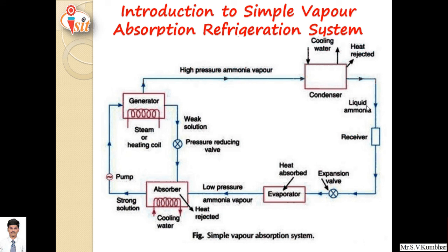This is the simple vapor absorption refrigeration system. Compressor is replaced by this generator and absorber unit. In the generator, we generally use a refrigerant plus absorbent solution. Most of the time we prefer aqua ammonia solution — ammonia is used as refrigerant and water is used as absorbent. The generator is heated with the help of heating coil, steam, or waste heat energy wherever available, due to which high pressure, high temperature vapors of ammonia are formed.